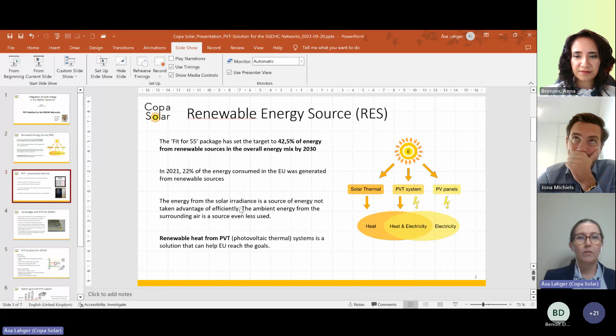Our PVT panel solution, shown on the right, has an absorber fitted on the backside of a PV panel. Instead of having only the installed electrical power of 420 watt peak, you can add 2,700 watt peak of thermal power as well. For example, installing a PV park with 371 panels fitted with the absorber on the backside would give you a thermal energy source of 1 megawatt peak. This solution is very suitable for the 5G DHC grid, and would provide the boost needed to stabilize the whole grid.